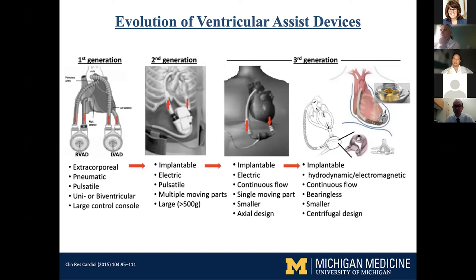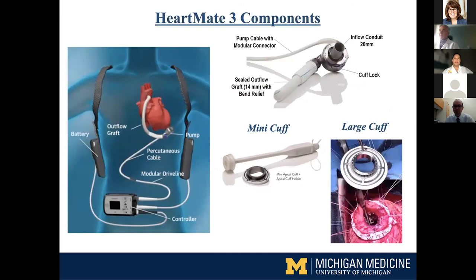Then came the hydrodynamic bearing, which instead of being axial is more like a centrifugal design — like a slingshot — where blood is shot outward. That was a different mechanism of continuous flow, but we still had problems with thrombosis and hemolysis. It was HeartMate III that arrived with a component basically suspended magnetically in midair, not touching anything. That prevented blood from warming up and causing thrombosis and friction, so thrombosis and hemolysis issues were much improved after that.